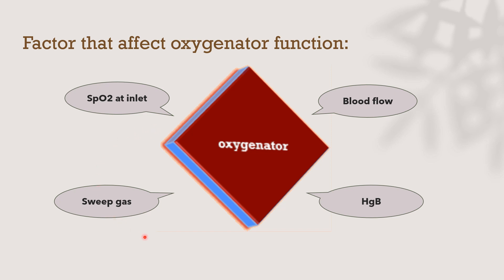The other elements affecting oxygenator function are components of rated flow: SpO2 at the inlet of the oxygenator, sweep gas FiO2, ECMO blood flow, and hemoglobin concentration. If we fix three of these and change one, we will see the effect on oxygenation and oxygen transfer in the next few slides.